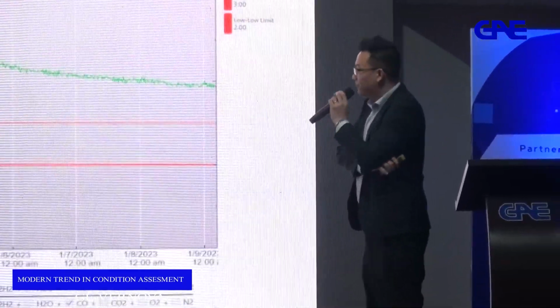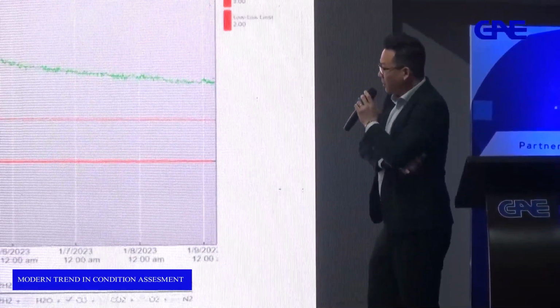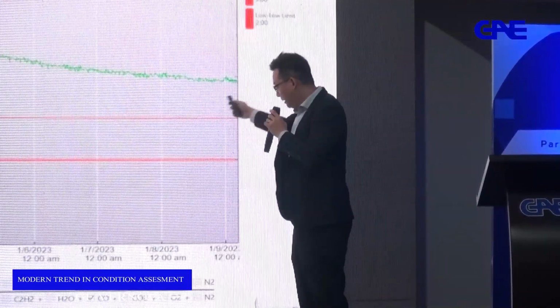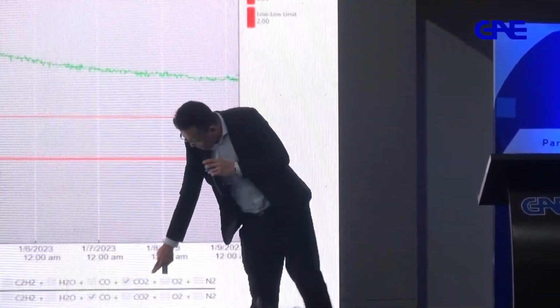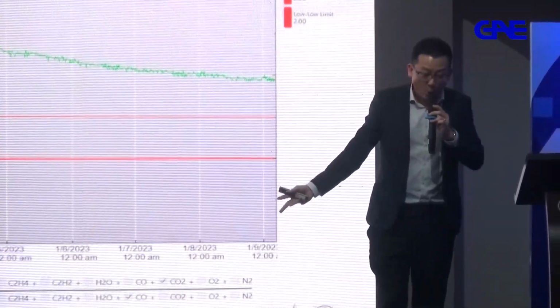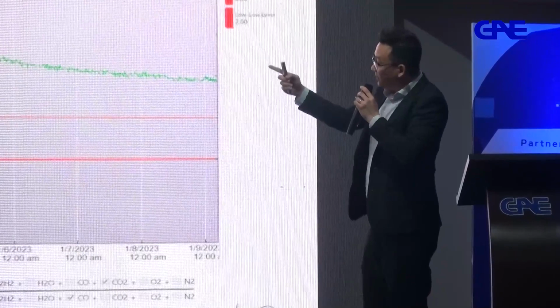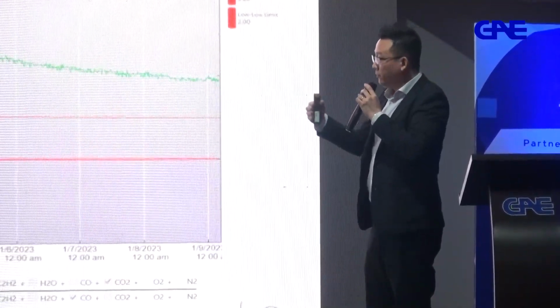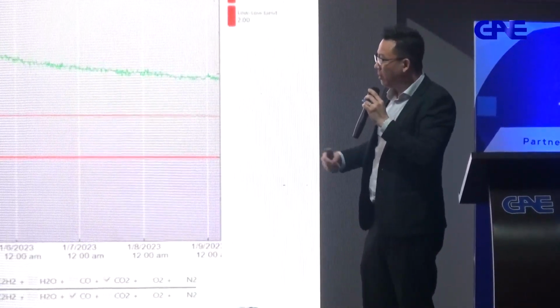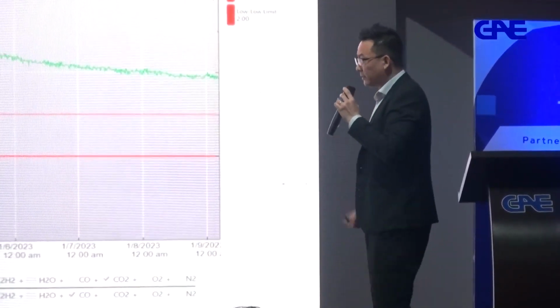So, carbon dioxide ratio. What we see over here, this is a very beautiful graph. It's looking at carbon dioxide against carbon monoxide ratio, CO2 over CO. So, what you see, excessive heat and moisture will cause irreversible deterioration of cellulose insulation. So a lot of time, if you remember, we keep on talking about that deterioration, irreversible.